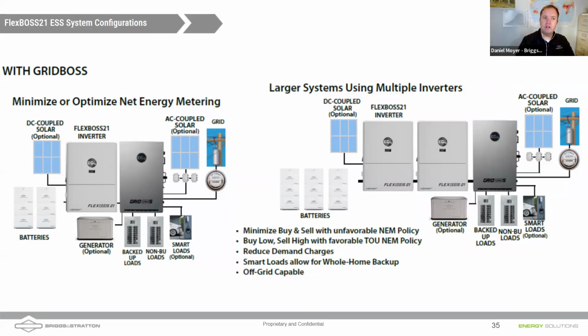So we're looking here at the optimized system on the left, with the Grid Boss and FlexBoss inverter. As I showed earlier, it has the ability to bring in AC coupled solar, backed up loads, non-backed up loads, smart loads, and also the generator. We'll jump in here in a second to see what it looks like when we leverage a Grid Boss, and how that makes systems easier, cheaper, and faster to install as well.